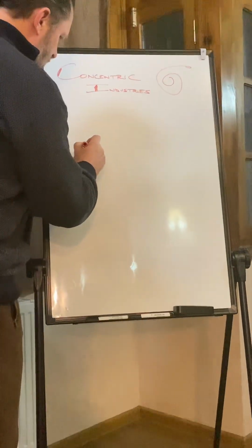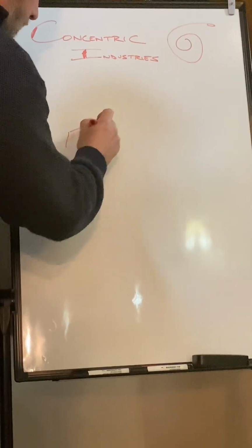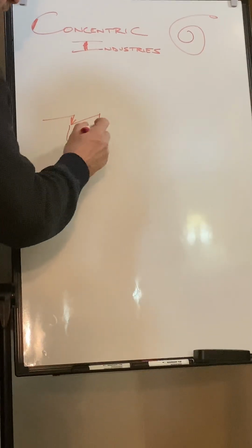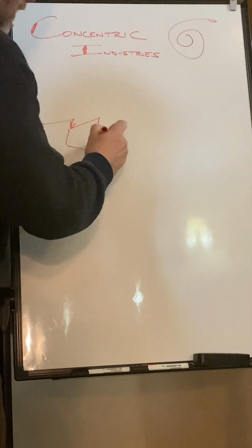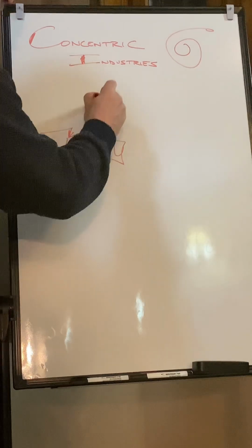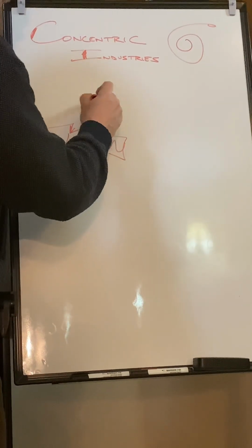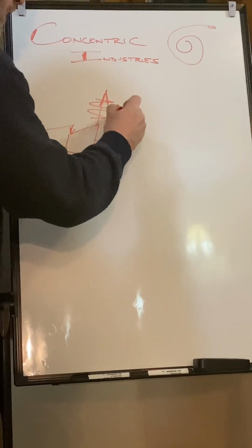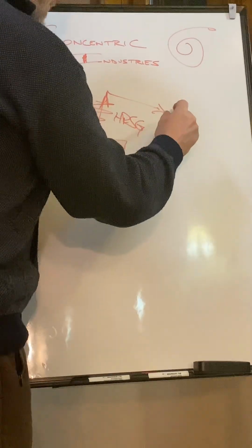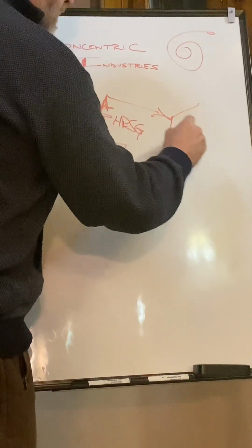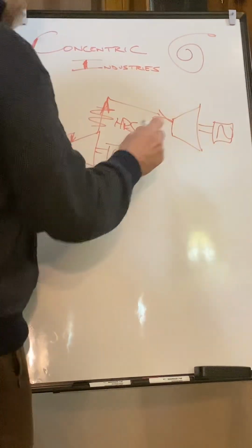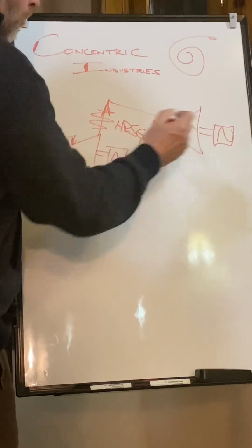Let's say you have a combustion gas turbine right here that is taking in natural gas as fuel, and it drives a turbine generator for electricity, and the waste heat comes off of that turbine into what's called a heat recovery steam generator. And then that steam comes in over here into a steam turbine generator and has more electric production, but without any new fuel production.